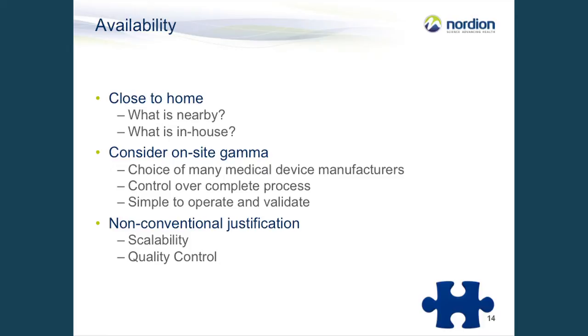A new innovative trend that we're seeing is companies using a non-conventional justification to bring gamma sterilization in-house. Their traditional model is of a large-scale manufacturing facility that produces enough volume of material to essentially justify a contract irradiator on their site. But more and more, we're seeing companies with smaller volumes but higher value products. In this case, the main driver might not be economic, although with the scalability of modern irradiator systems, smaller scale systems can still be affordable. Instead, the main driver is quality control over the process.